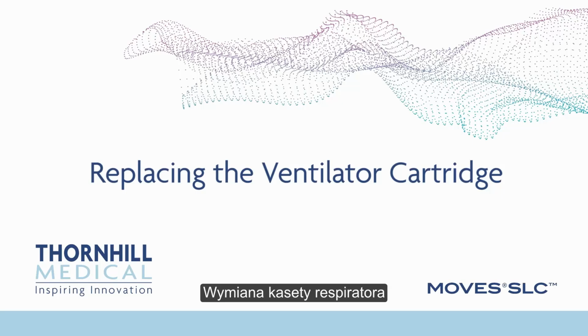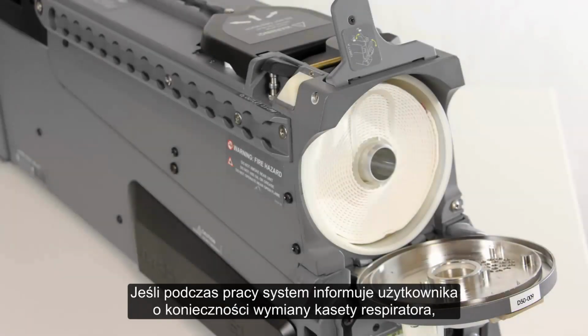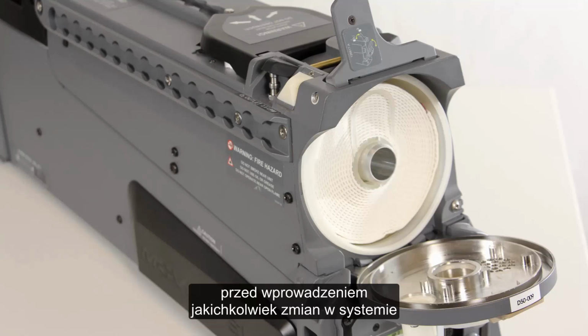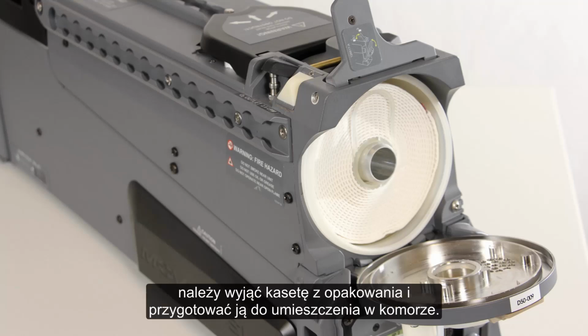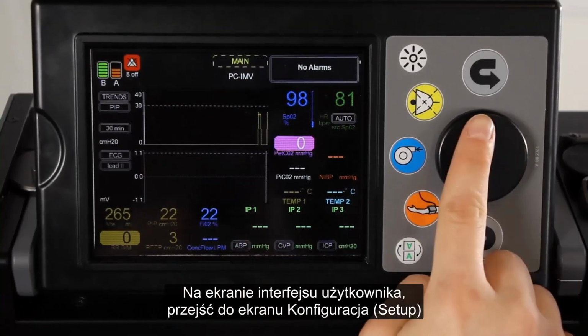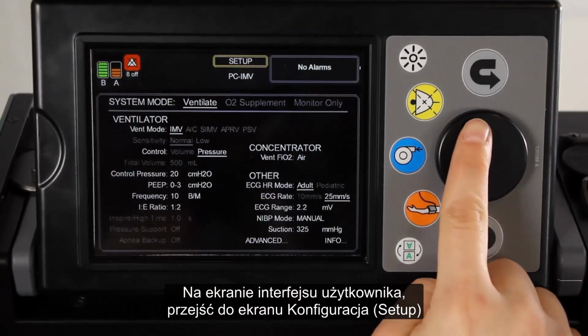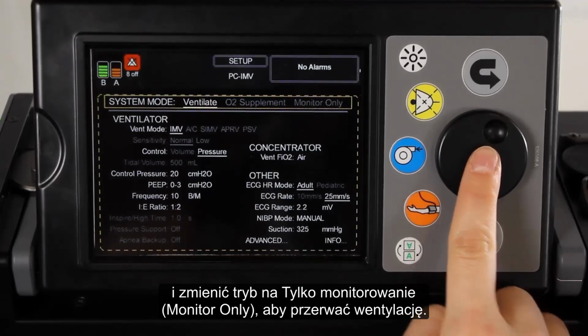Replacing the ventilator cartridge. If, during operation, the system is advising the user to change the ventilator cartridge, remove the cartridge from any packaging and have it readily available for insertion prior to making any changes to the system. On the user interface screen, navigate to the setup screen and change the mode to monitor only to stop ventilation.